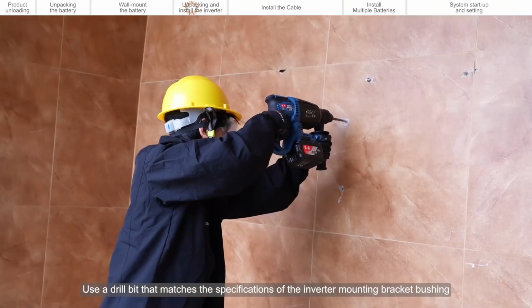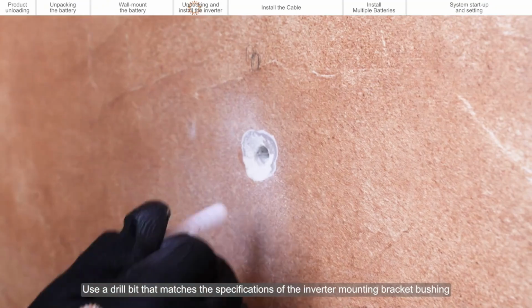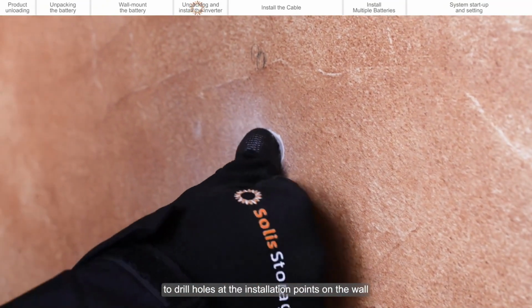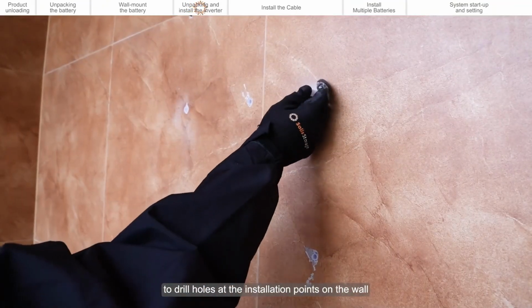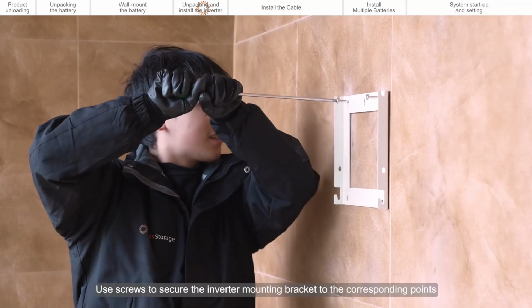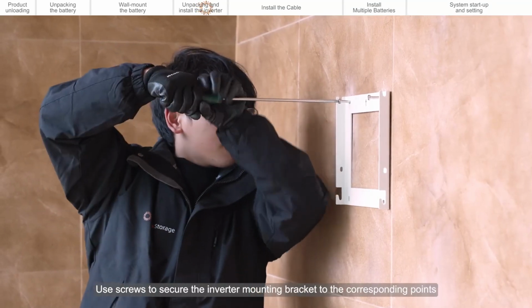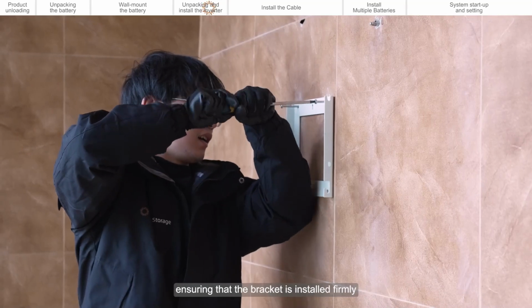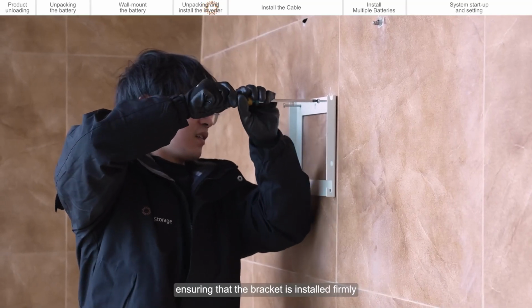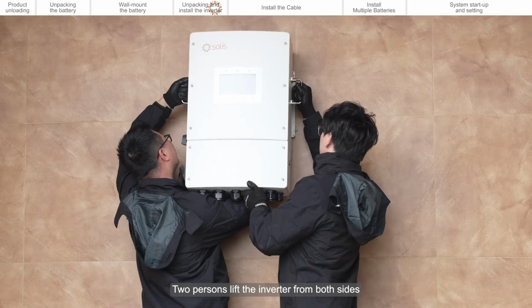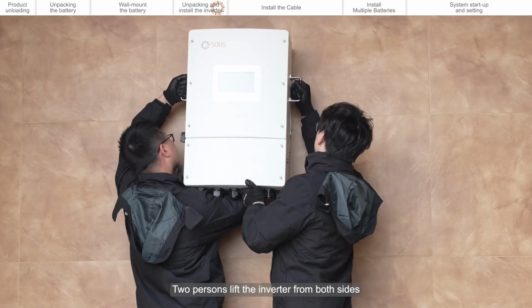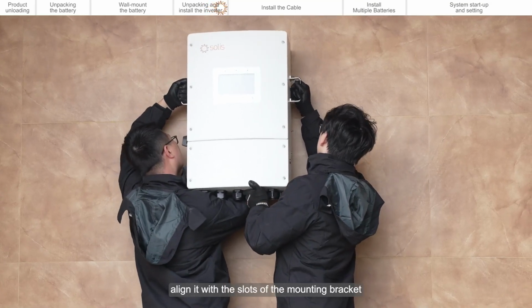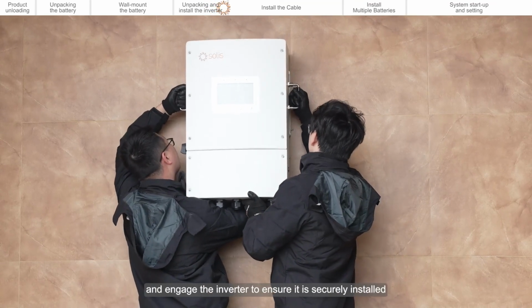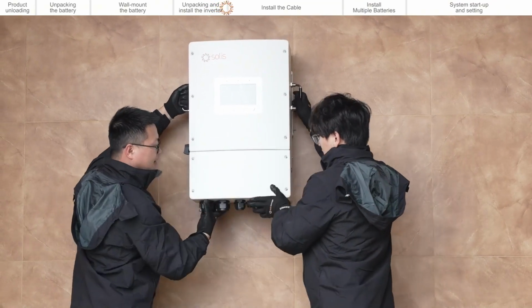Use a drill bit that matches the specifications of the inverter mounting bracket bushing to drill holes at the installation points on the wall. Use screws to secure the inverter mounting bracket to the corresponding points, ensuring that the bracket is installed firmly. 2 persons lift the inverter from both sides, align it with the slots of the mounting bracket, and engage the inverter to ensure it is securely installed.